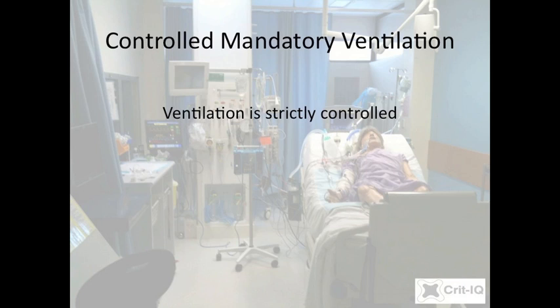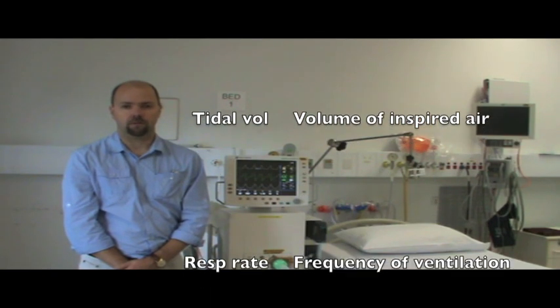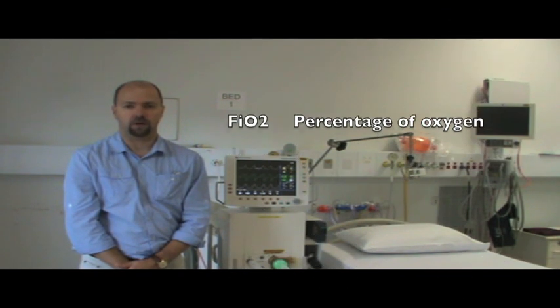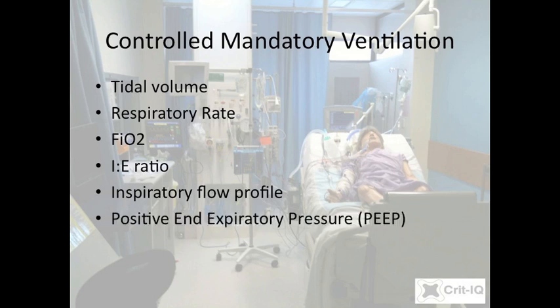In CMV mode, inspiration and expiration occur strictly according to these settings. CMV can be set as follows: the tidal volume — the volume of gas delivered each breath; the respiratory rate — the frequency at which those breaths are delivered; and the FiO2 — the fraction of inspired oxygen. Further settings include the proportion of time spent in inspiration and expiration, the profile of the inspiratory breath, and the PEEP — the pressure applied at the end of respiration. These concepts will be discussed in a moment.